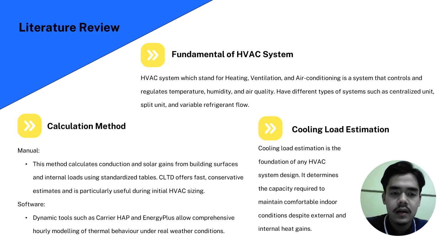Calculation method. There are two types of calculation method for cooling load estimation. Firstly, manual. The method calculates conduction and solar heat gain from building surface and internal load using standardized tables. CLTD offers a fast, conservative estimate and is particularly useful during initial sizing.